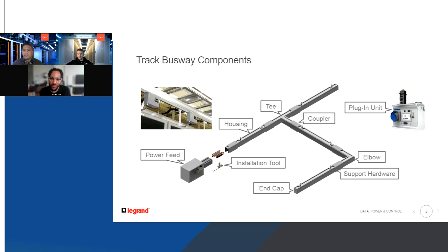I'll take that, this is Chris. No, we top out at 1,200 amps for the busway, so we would not have a 4,000 amp tap box available. Does the same thing go with bus duct as well? I imagine so, because those breakers would get pretty large. Yeah, so for bus duct right now, the highest tap off available is 1,250 amps. So it would not meet that 4,000 amp requirement.